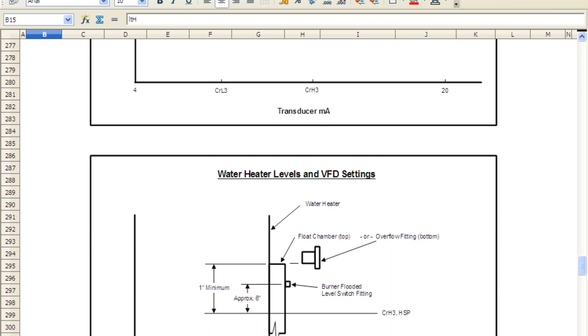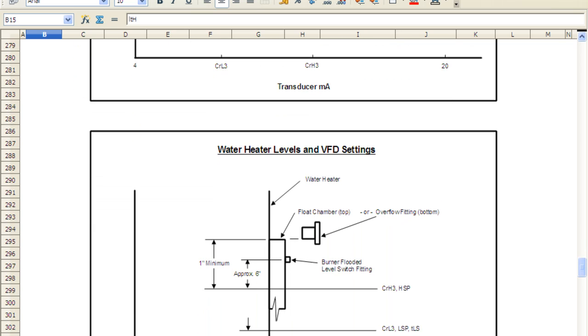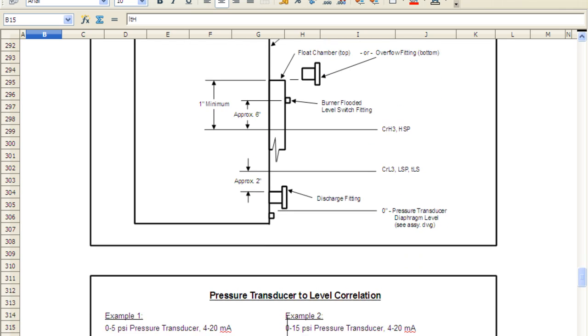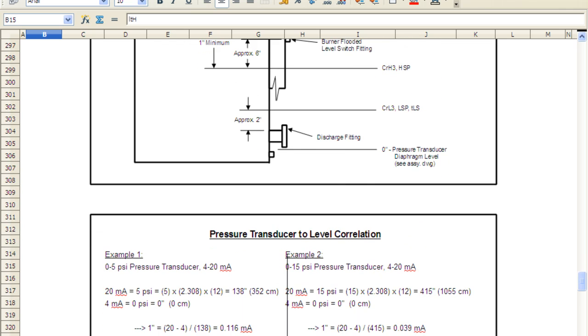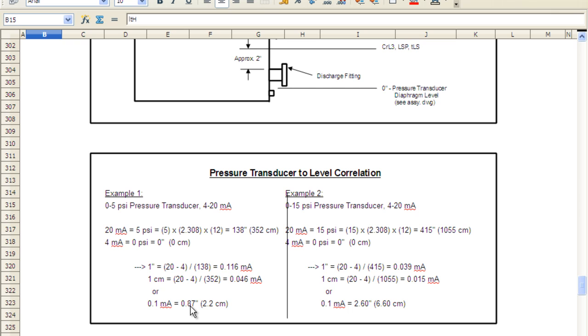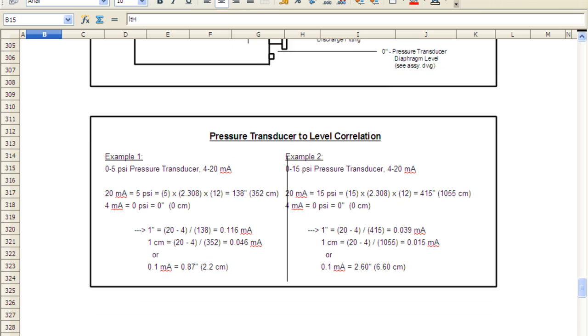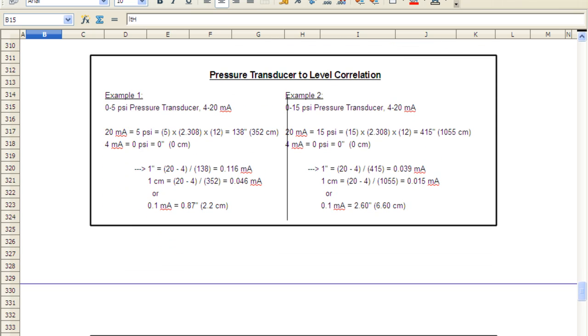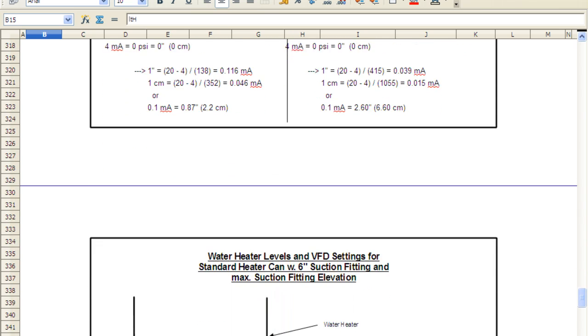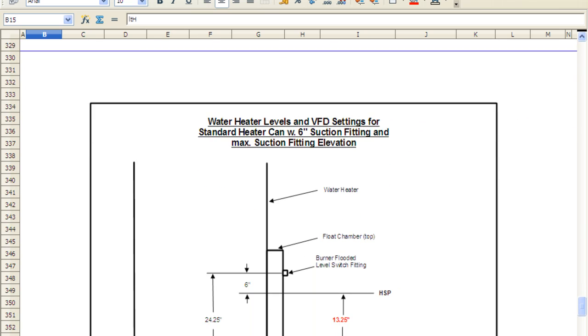Let's see what else we got down here. These are some calculations that are very helpful. We're adjusting in 0.1 milliamp increments. So in the adjustments we're going to look at in the parameter sheet above, every 0.1 milliamps that you change the number will change whichever level by 0.87 inches. So 0.1 milliamps equals 0.87 inches.